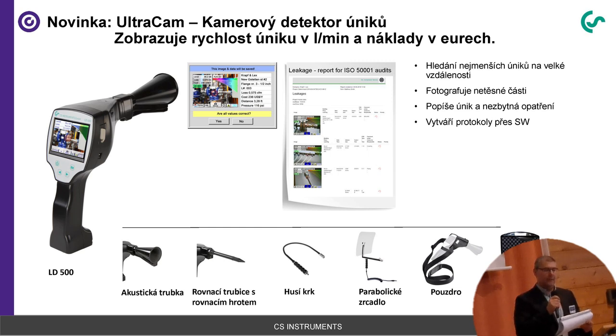And the nice thing is that the LD500 will show you the leakage rate in the display. Once you have found the leakage, it will show you the leak rate in liters per minute, and it will also show you the cost of the leak rate in euros per year. So you can decide: this is a big one, we have to close the leakage immediately, it costs a lot of money, or this is a small leak, we can wait. You can find the smallest leakages, it has an internal camera, you can photograph it, and then you can create a report. There is also software available, and with the software you can create a report, give the report to the people who are responsible for closing the leaks, and they can close the leaks. And then you can save the money.